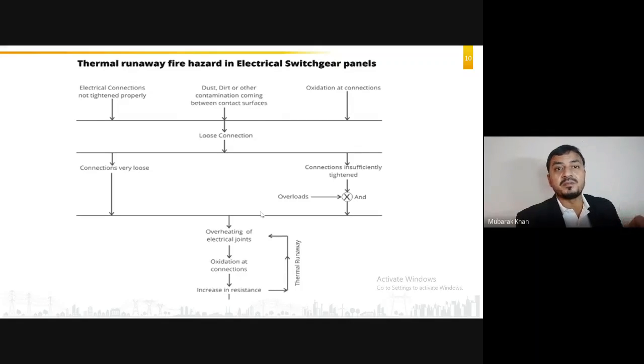It may not be, because under normal conditions all the joints may behave normally, but as the current increases, the voltage drop at that particular point will increase, and the resistance and the heating will increase. So insufficiently tightened joints are also very dangerous. Maybe after 2 months, 3 months, 6 months, or 1 year, your load will increase and your joint will give a flashover. So under both scenarios, there will be overheating of electrical joints.